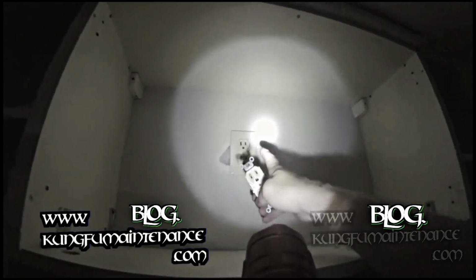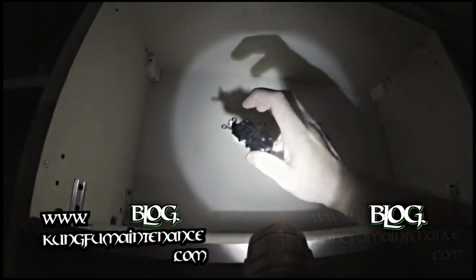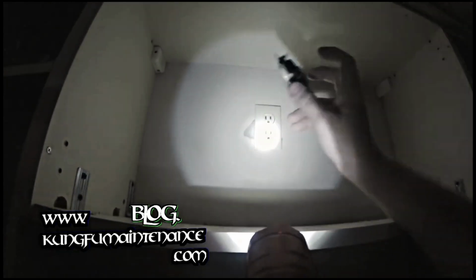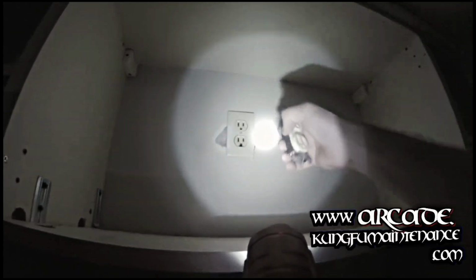But for this outlet, it's usually the line coming in and then the line coming out - line and load. The line comes in here and the load goes from the bottom over to the GFI. But because this basically burned apart, you can see the little burn mark there, it broke the connection, and therefore there was no power to the GFI.